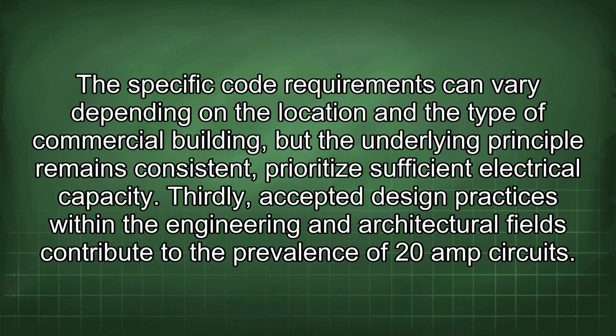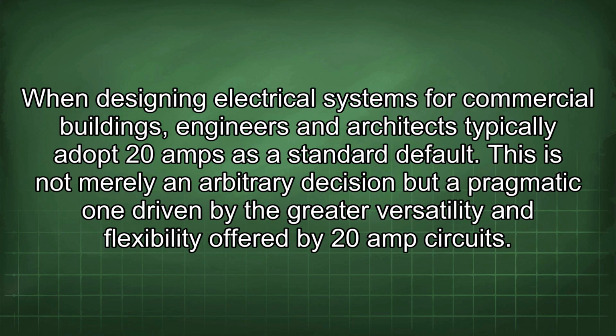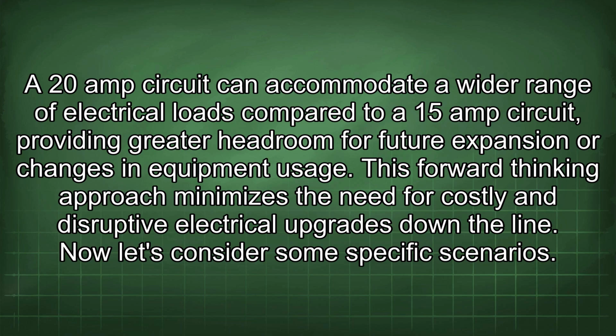Thirdly, accepted design practices within the engineering and architectural fields contribute to the prevalence of 20-amp circuits. When designing electrical systems for commercial buildings, engineers and architects typically adopt 20 amps as a standard default. This is not merely an arbitrary decision, but a pragmatic one driven by the greater versatility and flexibility offered by 20-amp circuits. A 20-amp circuit can accommodate a wider range of electrical loads compared to a 15-amp circuit, providing greater headroom for future expansion or changes in equipment usage. This forward-thinking approach minimizes the need for costly and disruptive electrical upgrades down the line.